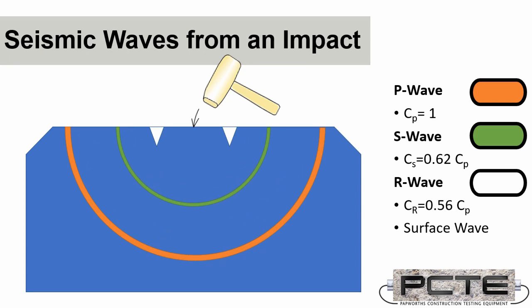We produce a number of different seismic energy waves. The compression wave is the fastest and is a direct compression and expansion in line with the strike. The shear wave is a side-to-side motion and is slightly slower. And the R wave, or Rayleigh waves, are a surface measurement. Impact Echo is a compression wave test, which is also known as P waves. And in particular, it's a resonant test of that.